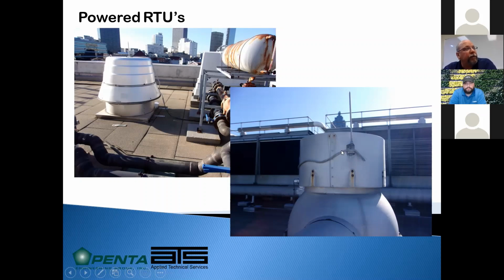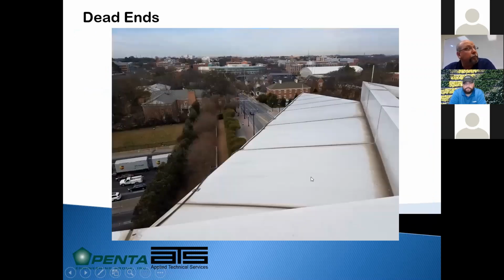The same with this unit. This was more than an 8 foot dead end, so we needed to continue this path and give it a second direction to go. On this facility, this was way more than an 8 foot dead end. So what happens is it just doesn't transfer the energy as quickly as it should. So this might not create the leader that we want it to create, and might not give it a favorable path to ground. So this corner is still not truly protected.